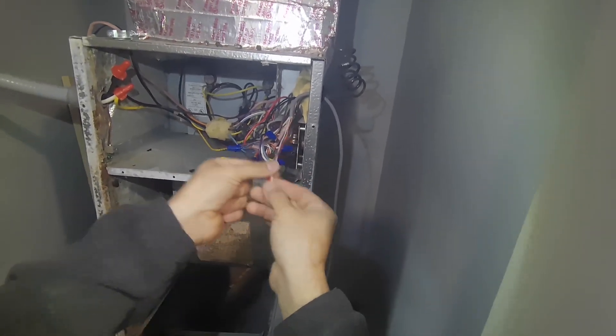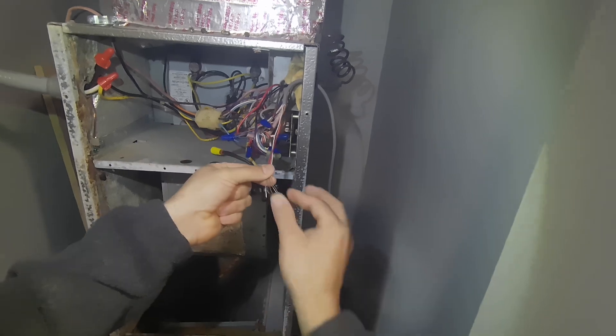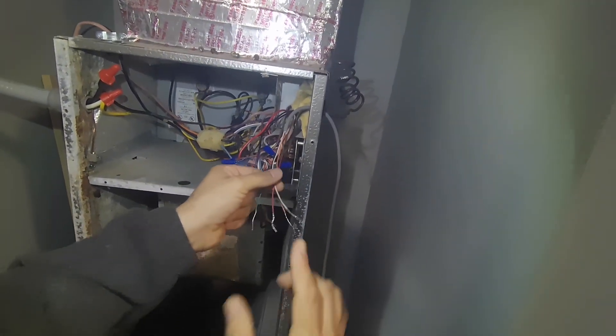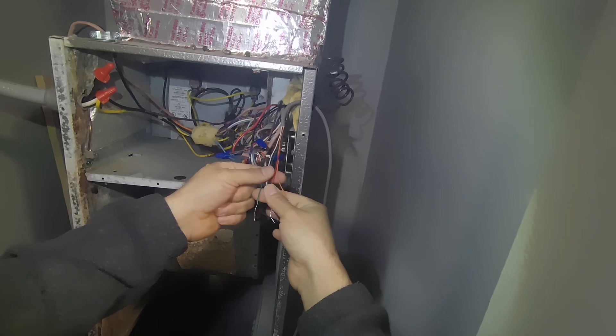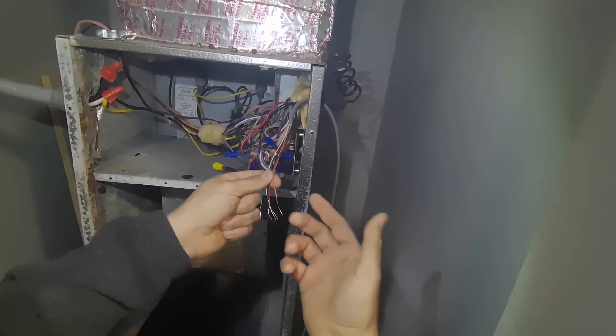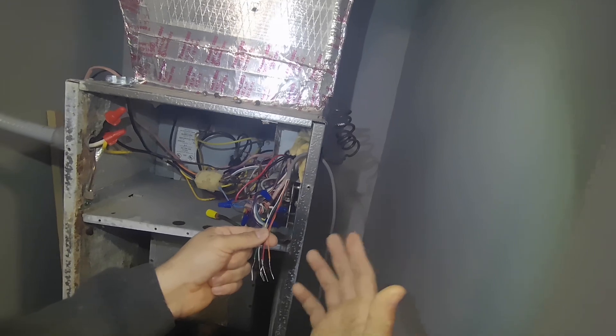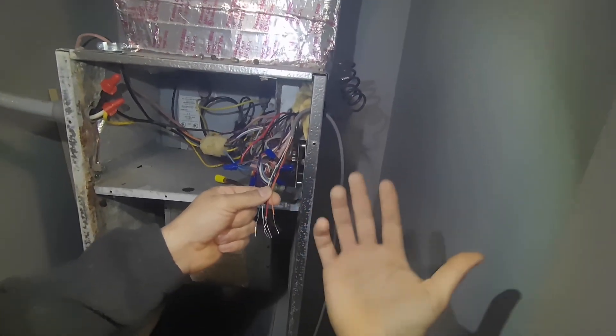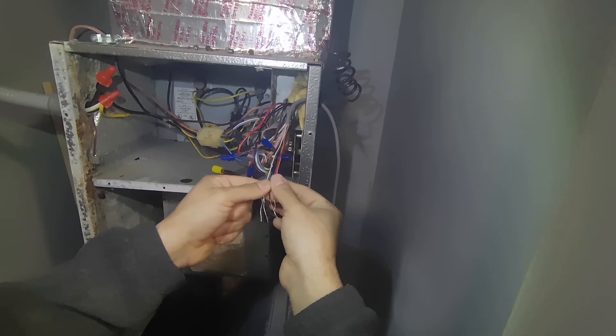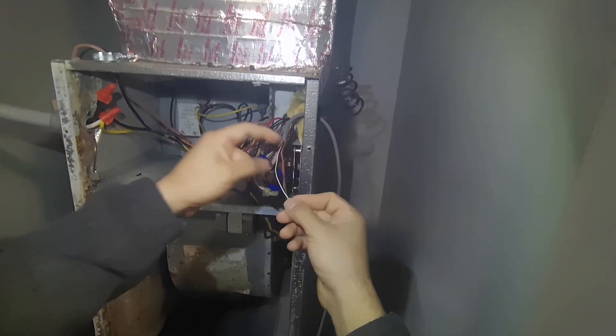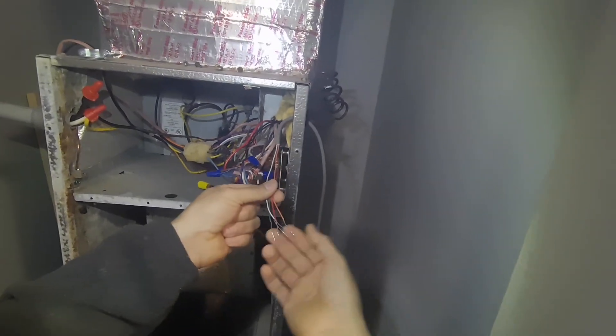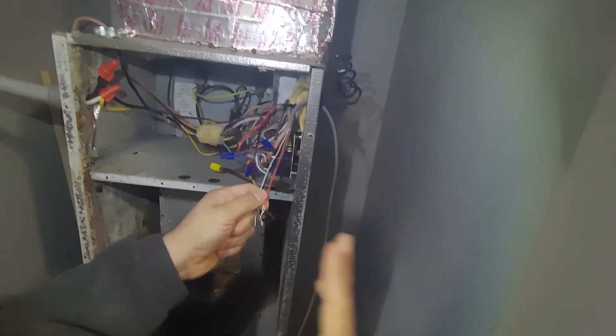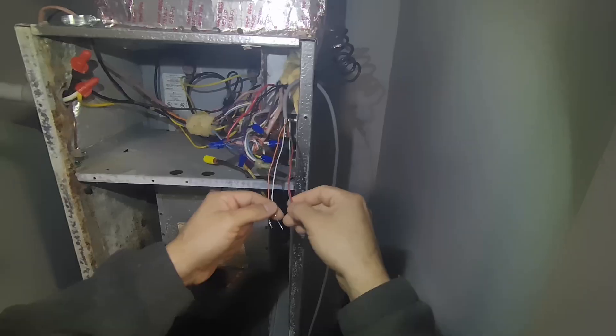Now if this was not long enough, you can always use a thermostat wire and just extend all of these wires together. I do recommend that you use every single color here when you do the extension with the thermostat wire, due to the fact that you could get confused and forget what colors you used if you end up taping them up and they're hidden. Just use every single one of these colors to make sure you don't get confused.